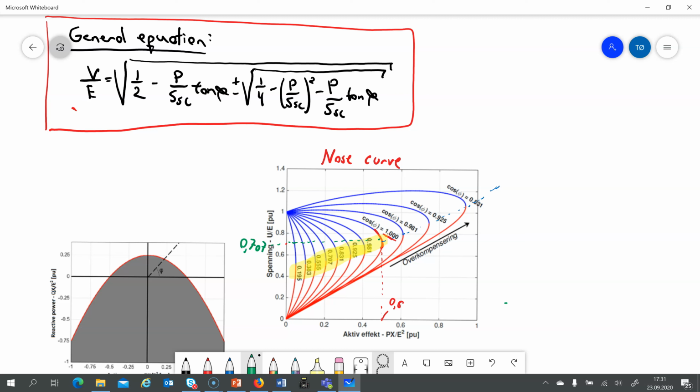And as you see, you have the 1 per unit voltage here. Typically, the voltage should be in the range of 0.9 and 1.1, like here to here. When we then compensate our grid system, you see that we will get this critical point, we call it here, will get higher, and it will get closer to the nominal voltage. So for example, if you look at this, the nominal voltage is actually here.